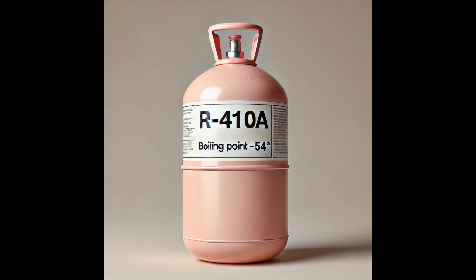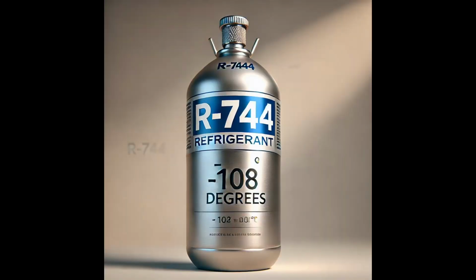No matter what style of heat pump you are using, the evaporator will be fairly effective at absorbing heat when the ambient temperature around the evaporator coil is 40 degrees or above. This is dependent on the type of refrigerant used in the system, but R410A is most likely what you will encounter. It works well in many climates in the United States. There are refrigerants with much lower boiling points. In fact, heat pumps can even operate in Arctic climates. They use R744, a CO2-based refrigerant, which has a boiling point of negative 108 degrees Fahrenheit.